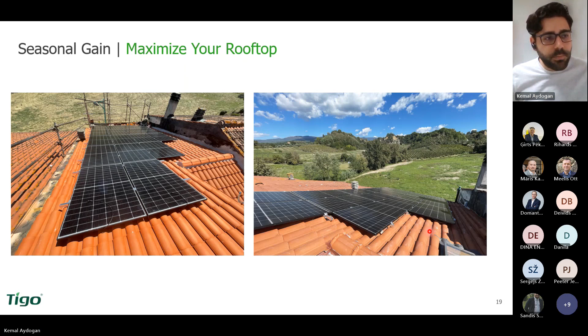But actually, this system can handle 1.2 kilowatts more, because TIGO enables the other PV modules to not get affected by the shadow. In February, the shaded PV modules produce as much as they can, but they don't let others down. For example, B6 is producing 17 watts while B7, in the same string, is producing almost 200 watts. It's the same for the A string: 26 watts, while normally the other PV module produces 210 watts. This is a momentary screenshot, but it's doing this all day.